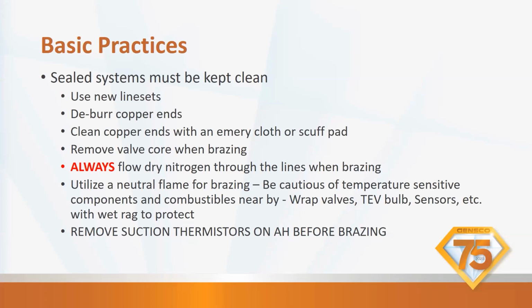There is nitrogen inside the coil. There is nitrogen inside your line set when you get it. So if you were to cut off the line set, plug it right into the hole, very little air is going to get in there. Very little moisture is going to get in there. So that when you flow your nitrogen through and braze, by the time you're ready to put on your vacuum pump, you're not going to have any air or moisture in there on a new system. Your evacuation is going to go very fast.